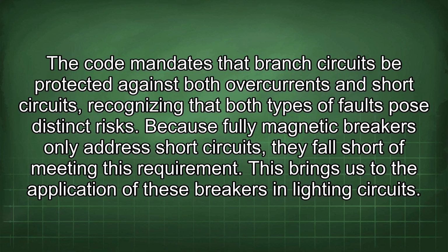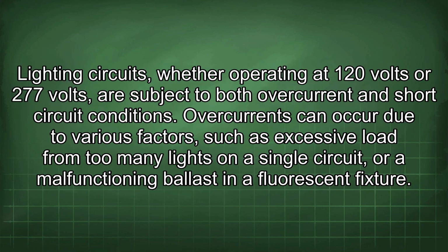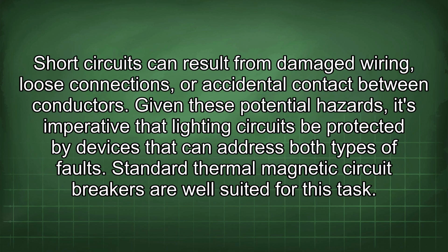This brings us to the application of these breakers in lighting circuits. Lighting circuits, whether operating at 120 volts or 277 volts, are subject to both overcurrent and short circuit conditions. Overcurrents can occur due to various factors, such as excessive load from too many lights on a single circuit, or a malfunctioning ballast in a fluorescent fixture. Short circuits can result from damaged wiring, loose connections, or accidental contact between conductors.